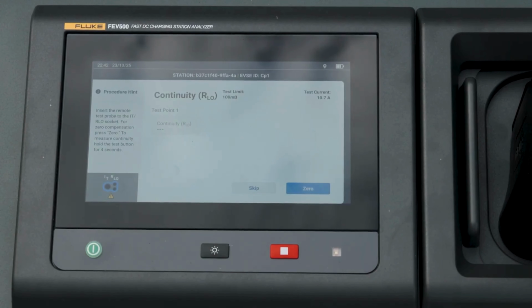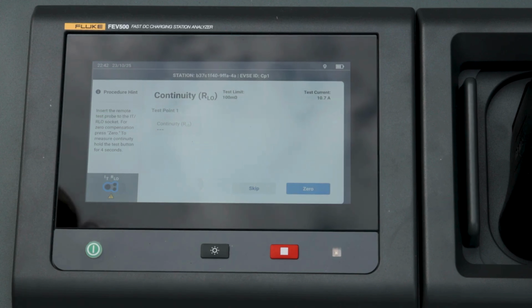Once you accept your zero offset measurement, you can use that throughout the duration of your inspection. So say you have 10 different charging stations to inspect on a site, you don't necessarily have to zero out your test lead every time.